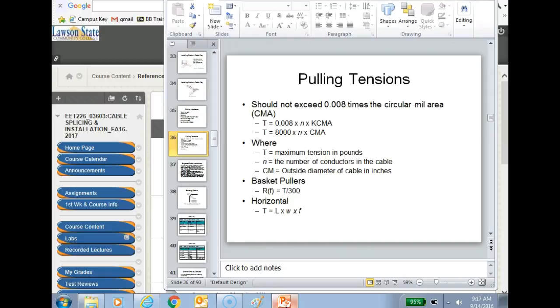And that's squared? So we take 0.008, multiply that times 20, multiply that times 0.004, which I'm taking for granted Chase is right. Does everybody agree with that, the KC mils for 14 gauge wire?